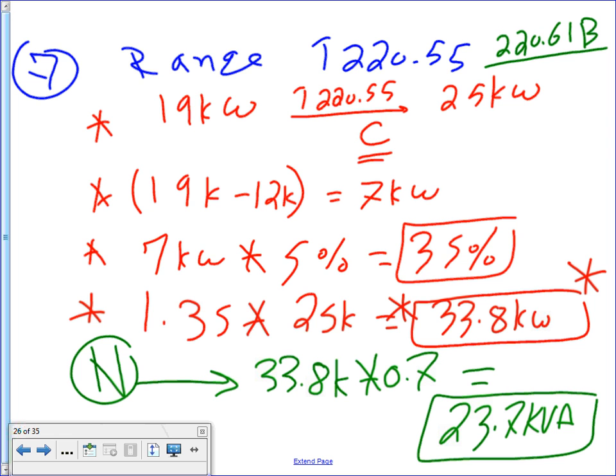Why do we chop it by 70%, guys? Because ranges are not just 240. They are 240/120 volt loads. So they have 240 for the heating elements and 120 for the control. Same thing for dryers. They call them 240/120. They're not just 240, they're 240/120, meaning they have a neutral on them.